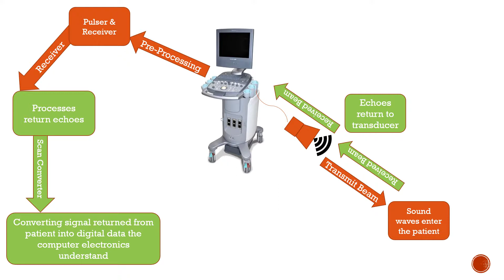Pulser is the frequency selection and output power, among other things, and then the receiver is what processes our return echoes. It is then transferred to the scan converter, which converts the signals returned from the patient into digital data that the computer electronics can understand. That is how the echoes are converted into an image that we can see on our screen.